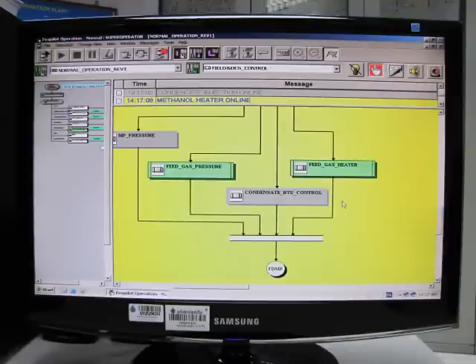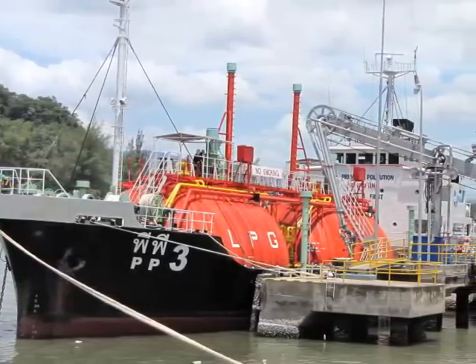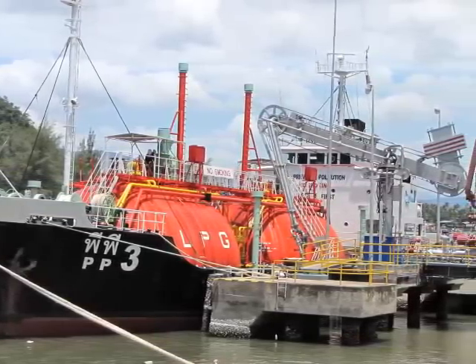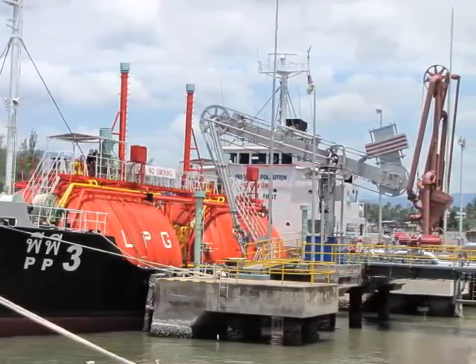The power plant uses gas from an offshore platform that is approximately 22.5% CO2. If this rises above 25%, plant efficiency goes down. ExaPilot maintains CO2 within agreed levels, keeping the power plant customer satisfied and increasing LPG yield by $450,000 per year. ExaPilot also controls the venting of loading pumps and controls product flow during LPG and natural gasoline ship loading, reducing electricity consumption and preventing LPG product loss.